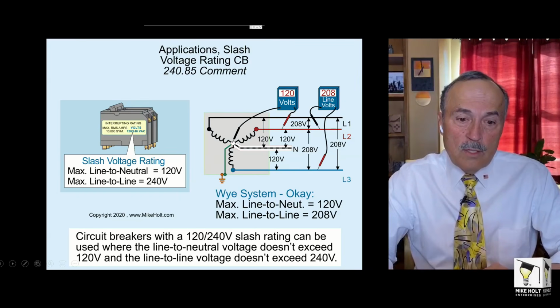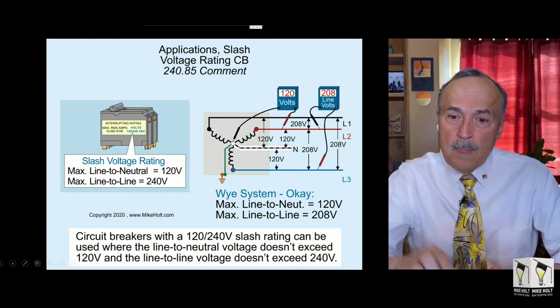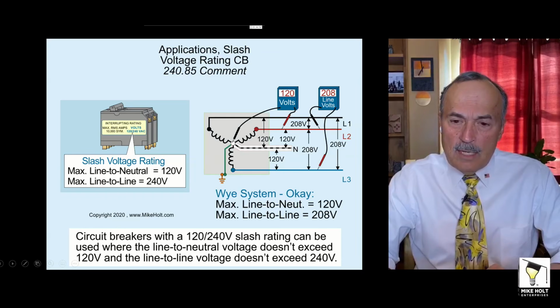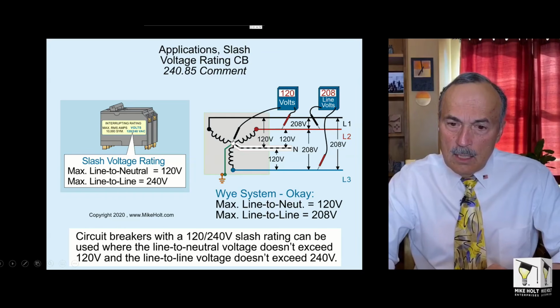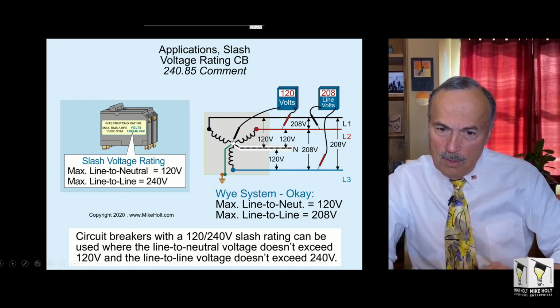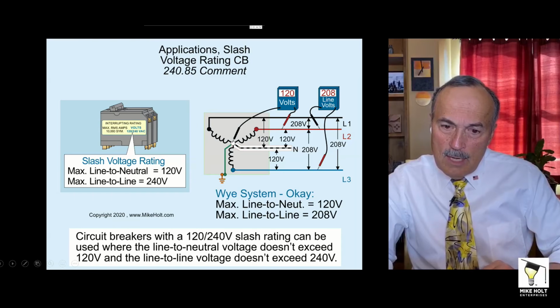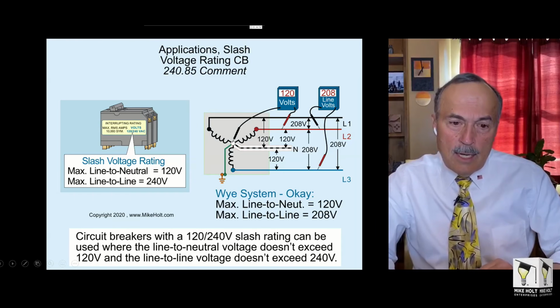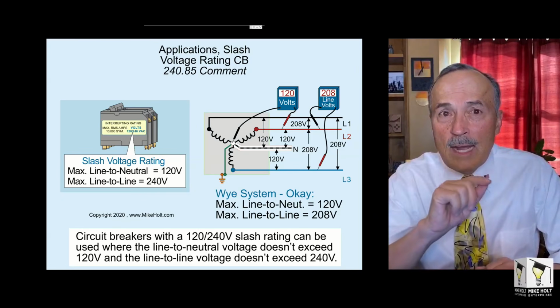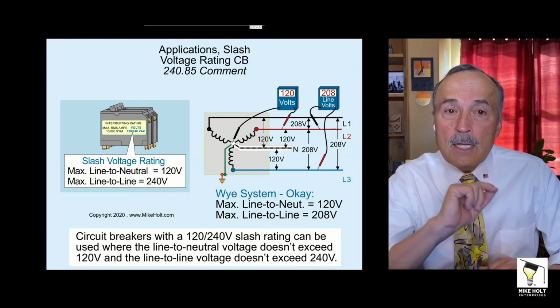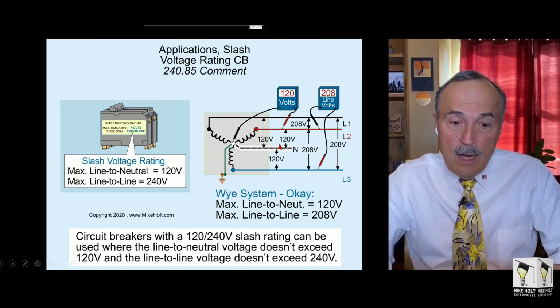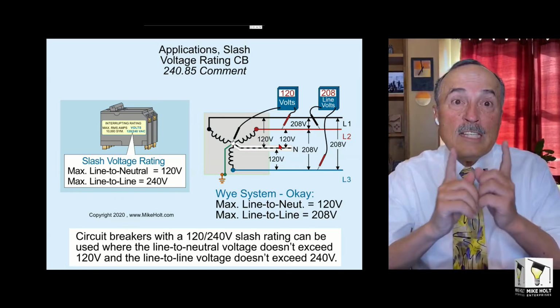If it's a slash rated breaker, like a 120/240 volt slash rated breaker, make sure that it's suitable for the system. Now, the maximum voltage between any one line, this line right here, and ground is 120. And 120/240 means the maximum line-to-ground voltage of a fault is 120. Well, of course, in a Y system, that's fine. Now, the higher voltage of the slash means the maximum phase-to-phase voltage under a fault condition. Well, 208 is the maximum, so guess what? A 120/240 volt slash rated breaker is perfectly fine to be used on a 120/208, 3-phase, 4-wire system.